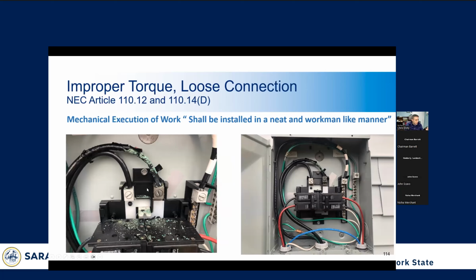This I think is the most interesting error in this presentation. These are 2 pictures side by side of the same panel. This is installed outdoors. You can see one side of this looks a lot better than the other side. And this lug over here on the right is discolored. What happened is the contractor did not tighten the lug. So this was just loose in the lug, and it would sometimes have a good connection, sometimes a bad connection. And so the wire would heat up and cool down, heat up and cool down, and it caused failure of the insulation of the wire. Then the wire was exposed and it's outside, so it's very moist and it corroded. And then pieces of the corroded copper started falling off, as you can see here.